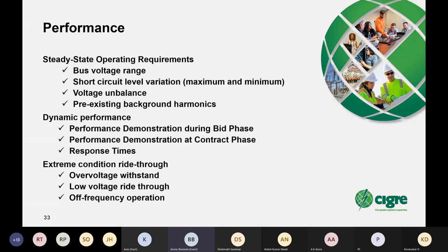basically three categories of performance: steady state operating requirements, where you're looking at extremes of bus voltage range, extremes of short circuit level, maximum and minimum, extremes of voltage unbalance, maximum unbalance, pre-existing background harmonic levels. And on the dynamic side, where typically you specify a level of performance that you need in terms of response times, fault recovery response, damping, whatever your performance requirement is, as you determine in your studies.